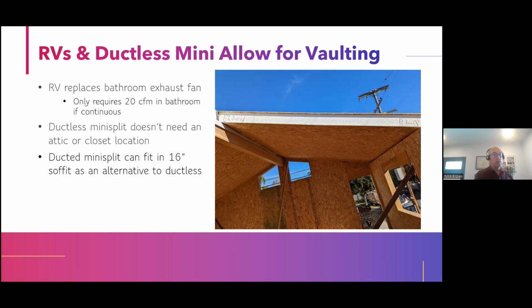We don't need a bathroom exhaust fan because, and this was a question earlier, if we put 20 CFM of exhaust in a bathroom with our recovery ventilator running continuously, we meet the spot ventilation requirement. Don't let the building department tell you, no, you need a bathroom exhaust fan, minimum 50 CFM, because they're wrong. I had to show my building department the code language where this exists. So I was able to vault the ceiling in my bathroom. I was able to vault the ceiling in this whole ADU, which really makes the place feel better.